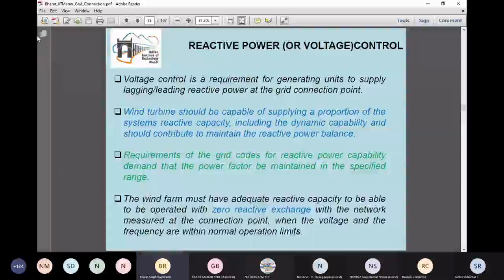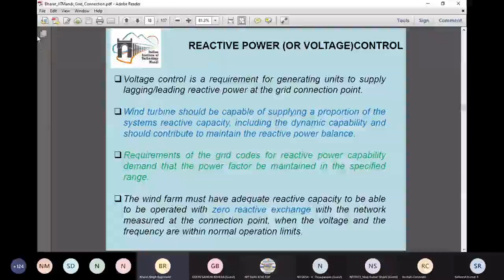They should not be either taking or injecting reactive power. But our wind turbines are most of the time made up of induction generators, which for their operation require reactive power rather than feeding it into the grid. So this is a very difficult situation for such a wind energy conversion system. But with the utilization of a power electronic converter, it is possible for the induction generator with the converter to produce reactive power for its own consumption as well as inject it into the grid.